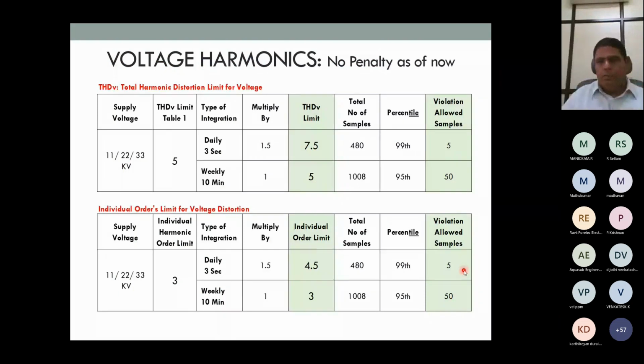This is the tabular column which we have arrived at using those sentences told in the last slide. Say, for example, if a consumer is connected at either 11, 22 or 33 kV, his voltage THD, voltage harmonic limit, is 5%. So there will be two types of integrations. Readings will be taken, one on a daily basis and the other for the whole week. So the integration is 3 seconds. Every 3 seconds there will be a reading recorded in the meter, and the other reading will be every 10 minutes.